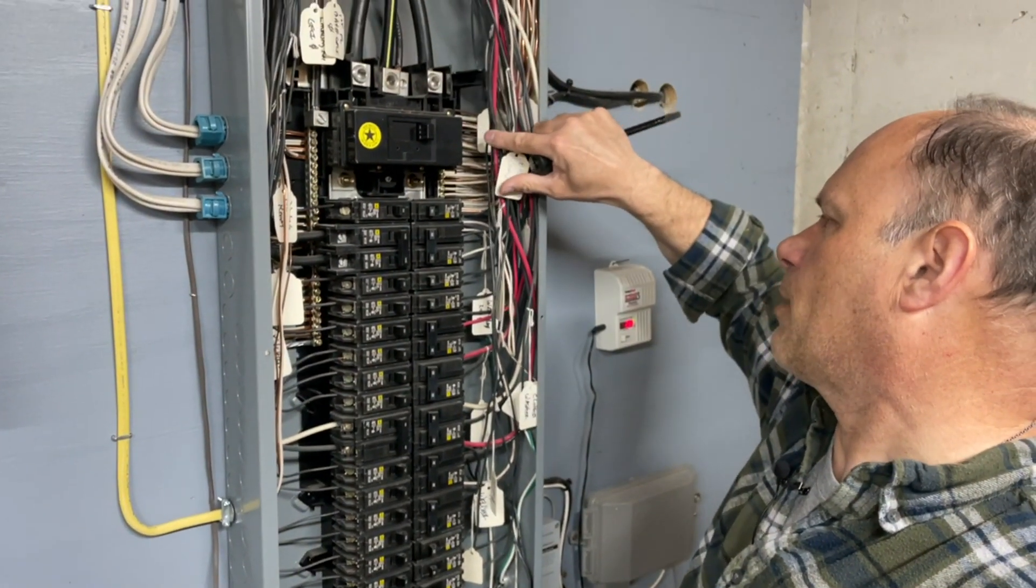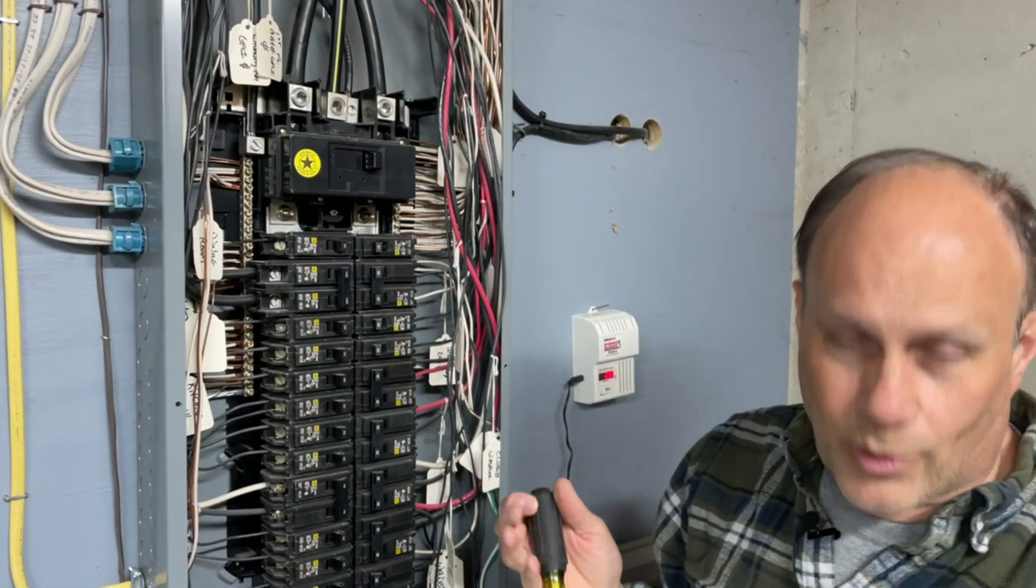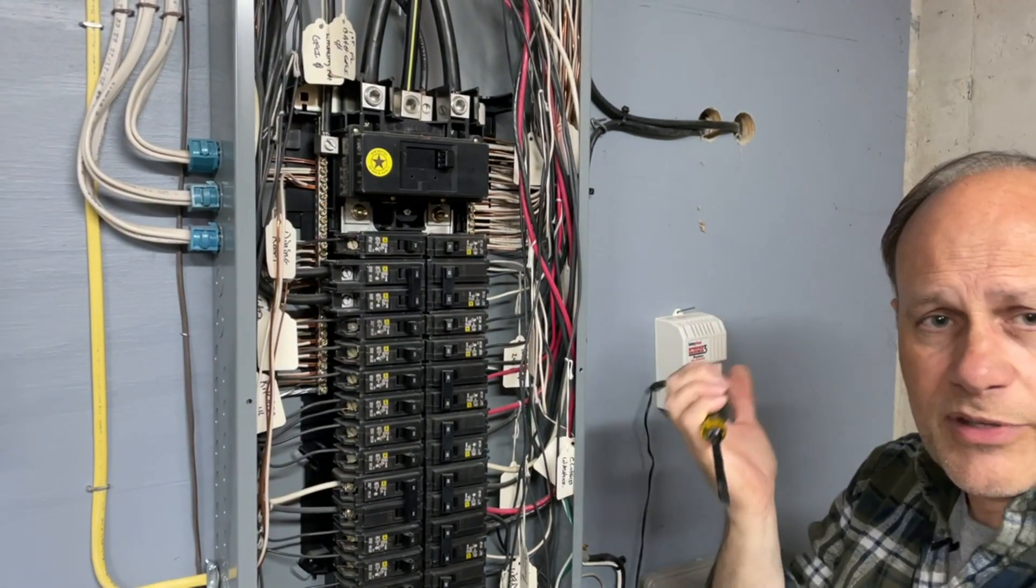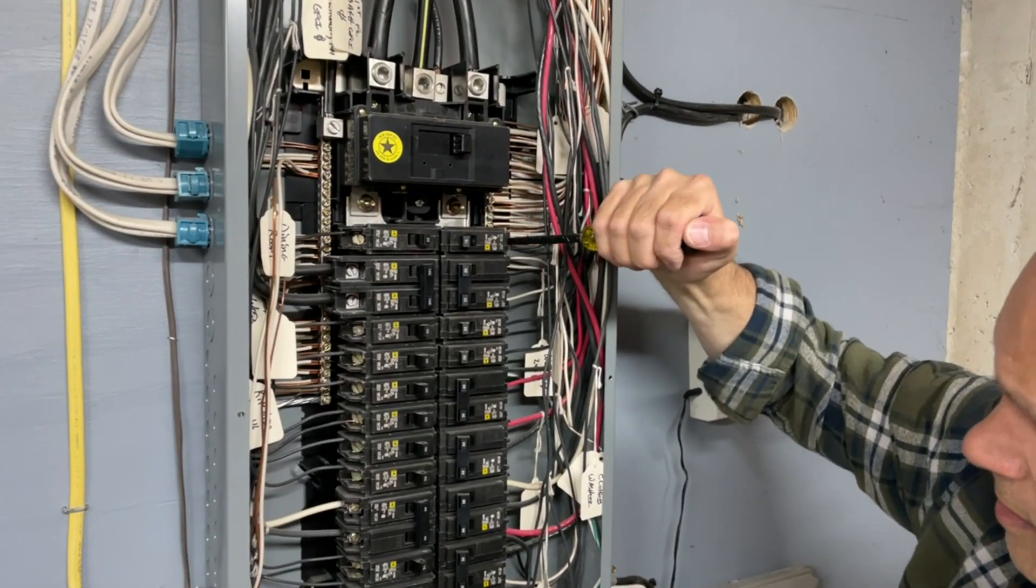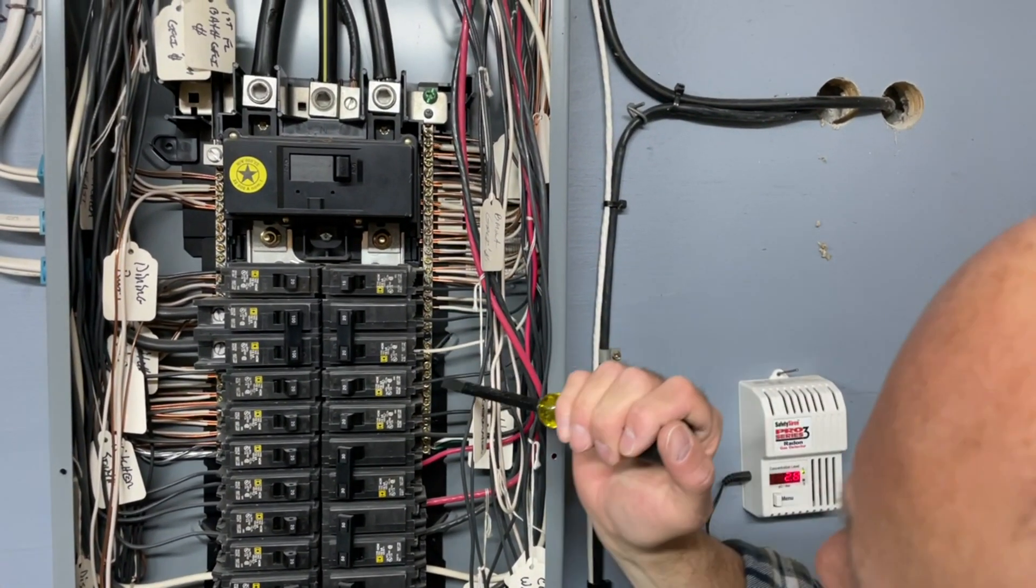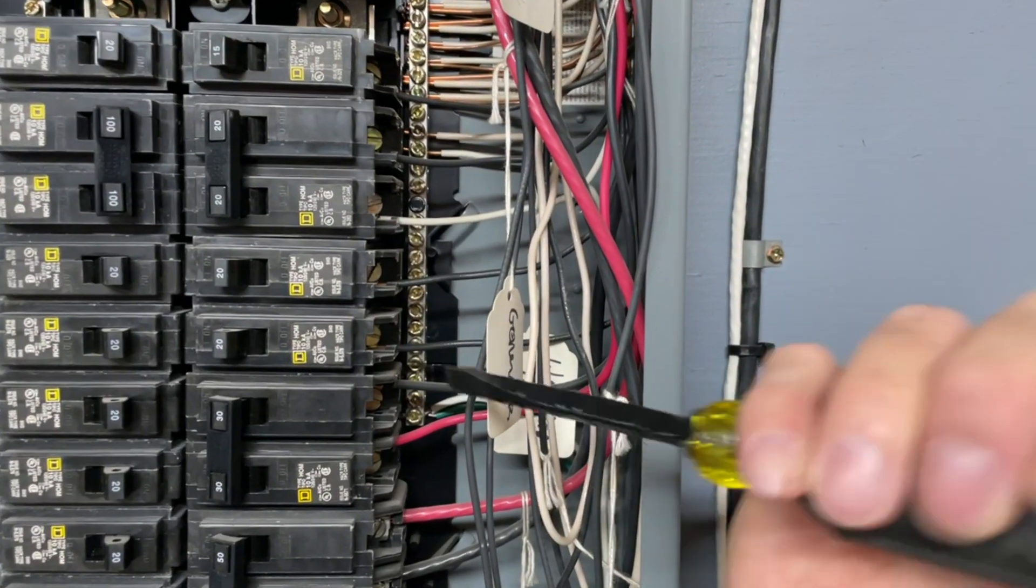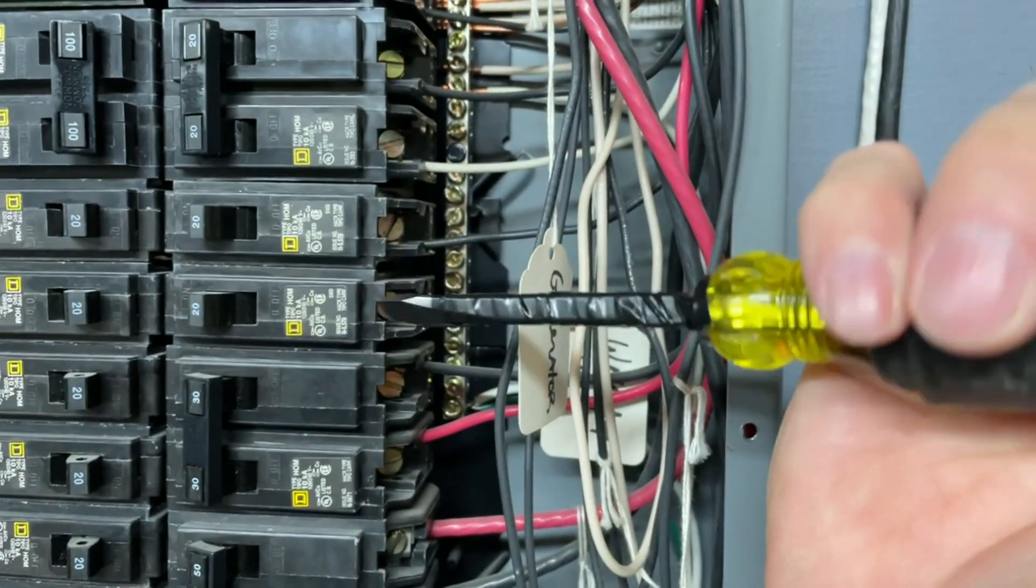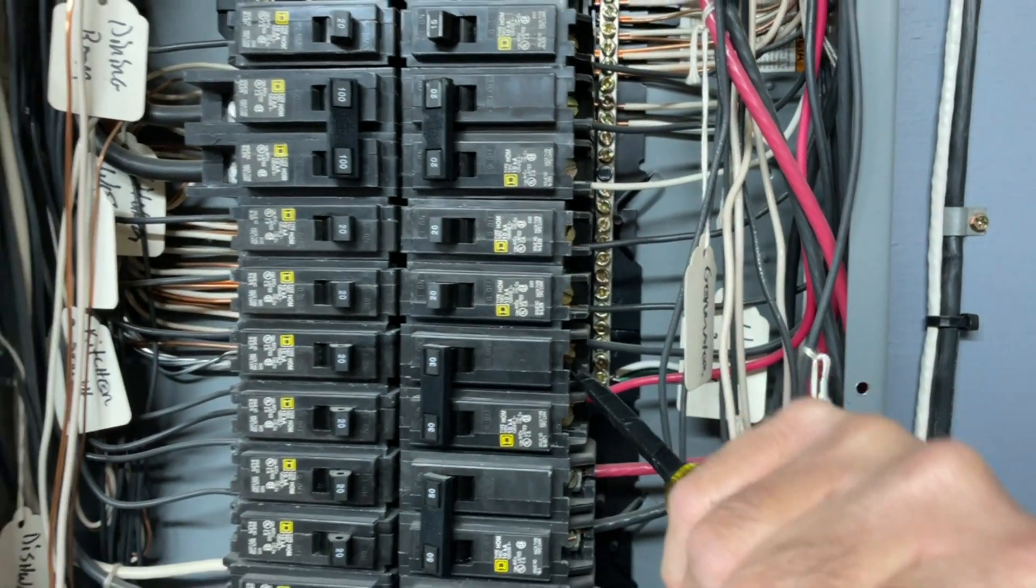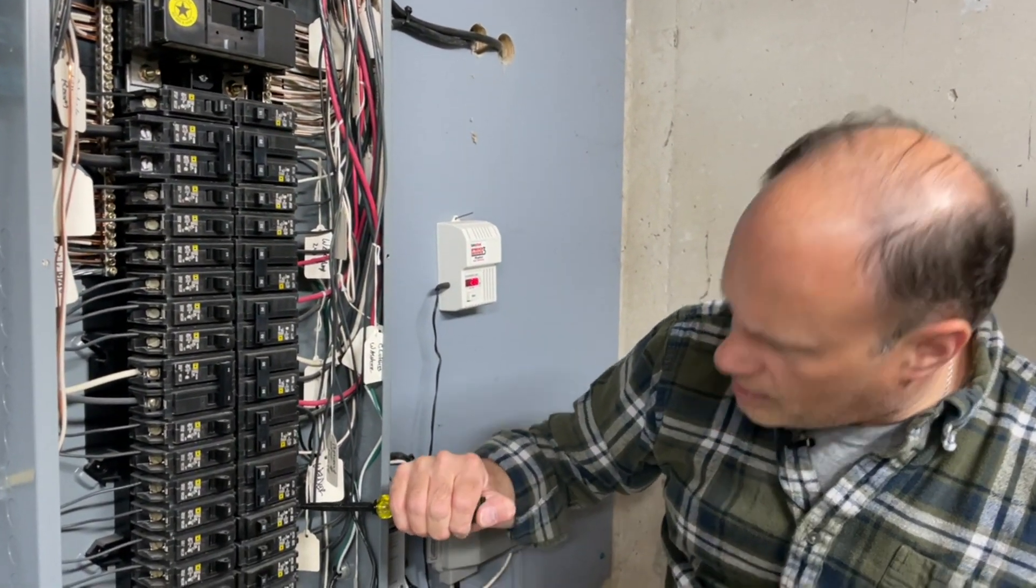So what I'm going to do is I'm going to go through the circuit breakers first. And you can see that I have my screwdriver insulated. I have one hand in my pocket. You do not want to be doing something like this. Your hand slips down the screwdriver. So I always have one hand in my pocket, so I'm not grounded to anything. And I can try to tighten these down. All these connections are tight that I can see. And you can see, I can see where the screw terminal is. So I'm not going in like this and fumbling around. I already have my screwdriver oriented. So I'm going right into the slot on that breaker and I'm turning it. That one moved a little bit. These are all pretty tight. These are all very tight.